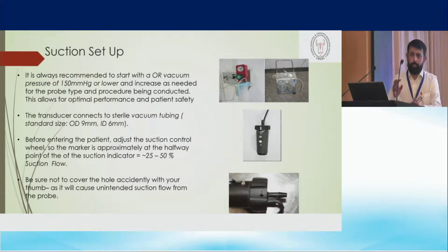One important point I want to highlight regarding managing this device is managing the suction. Many of our colleagues who have used this device are not satisfied, maybe because of inappropriate use of suction. There is a suction control knob at the back side of this transducer. You have to adjust the knob almost in the middle so that the irrigation is not sucked completely. If the water is not there, then the vision is lost. The mucosa falls on the tip and you are lost, and then the device is not used appropriately. So managing suction is a very important part of using this device.